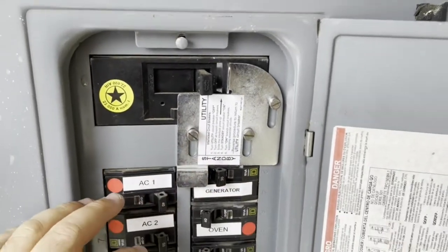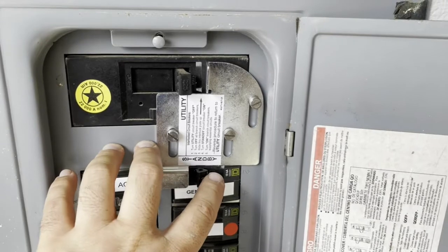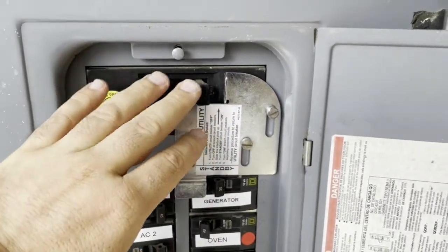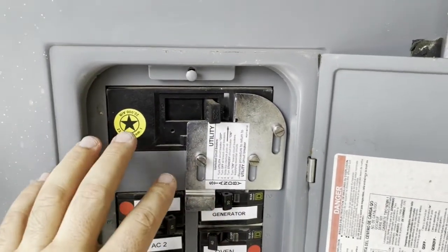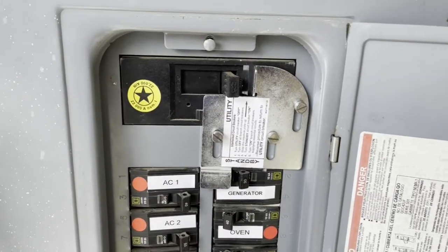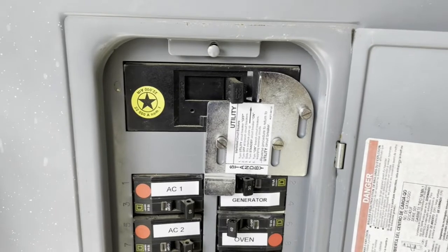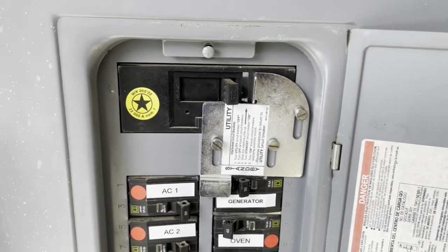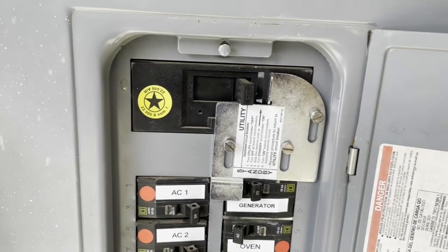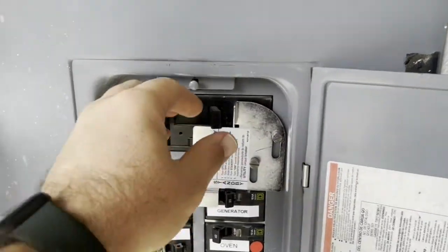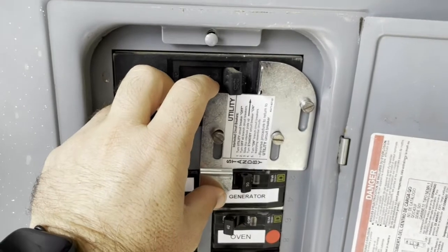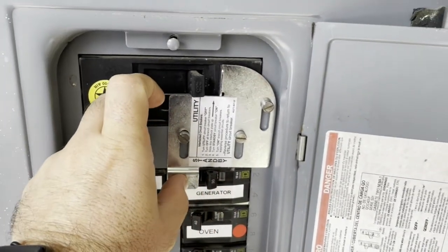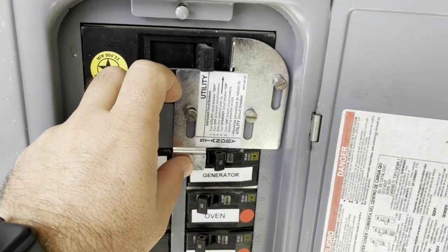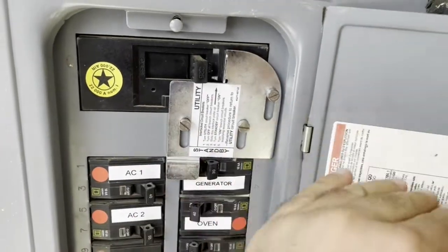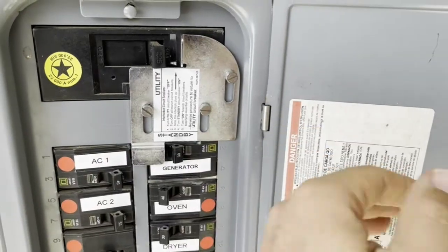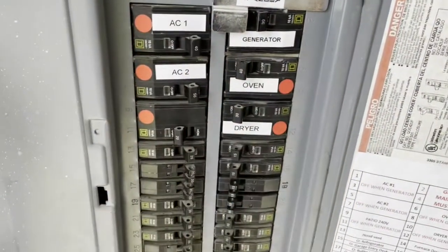The purpose of this is to prevent you from flipping up the generator switch while the mains is on, because if you keep this on and then run the generator connected to your panel, you'll be backfeeding the grid with your power. That can create safety issues for maintenance people working on the grid, or your generator simply won't be enough to feed the whole neighborhood. So once you flip this switch off, you can move this up, and only then can you turn the generator power switch or circuit breaker on, which feeds our panel in a reverse manner. Instead of power going from panel to load, this time it comes from the generator and feeds all this power.